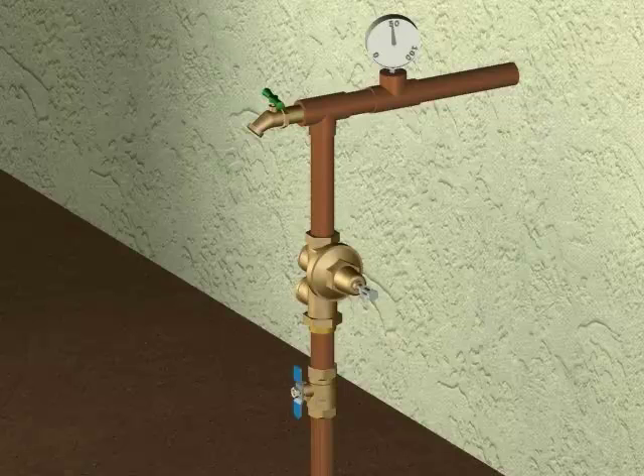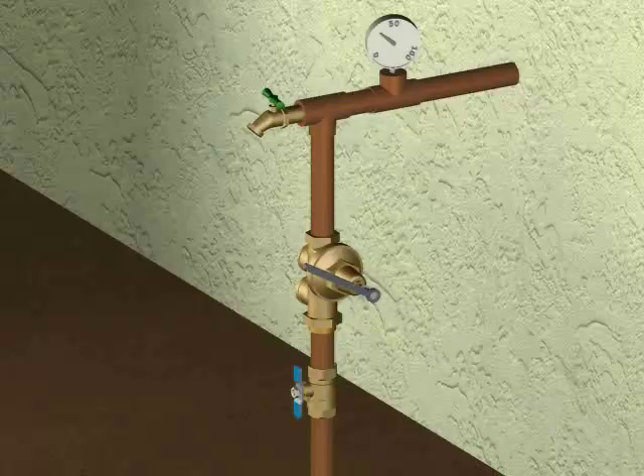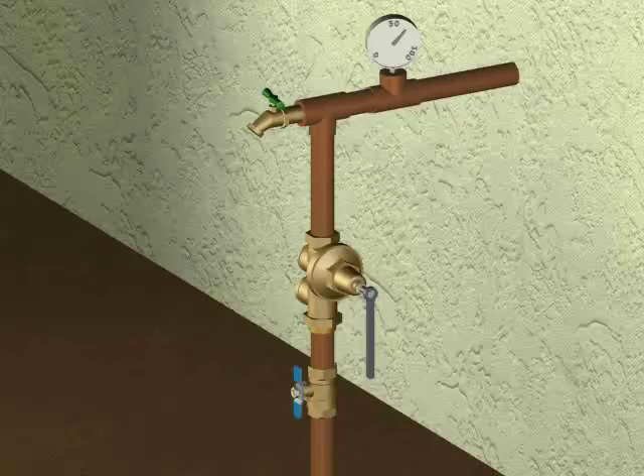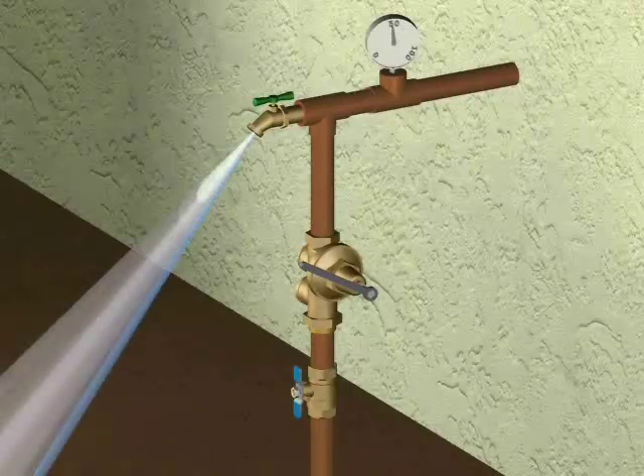If necessary, adjust your outlet pressure to 50 psi. The outlet pressure is raised by turning the bolt clockwise into the bell housing. To lower your outlet pressure, turn the bolt counterclockwise and then open a faucet to relieve pressure and check the actual setting.